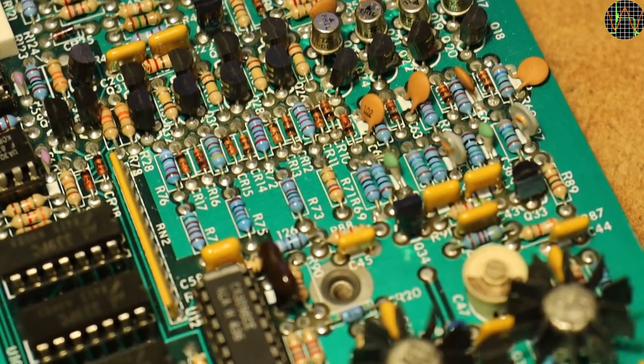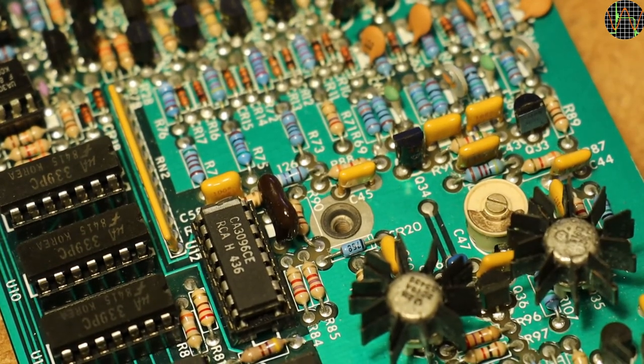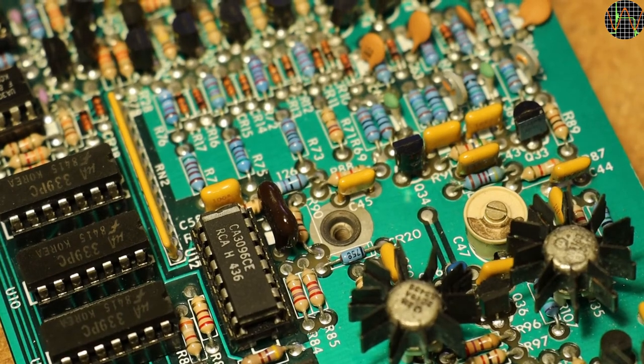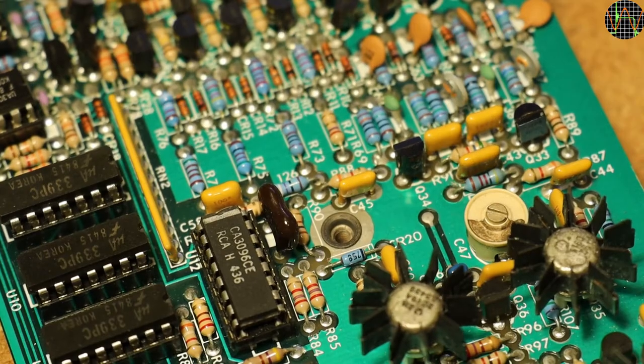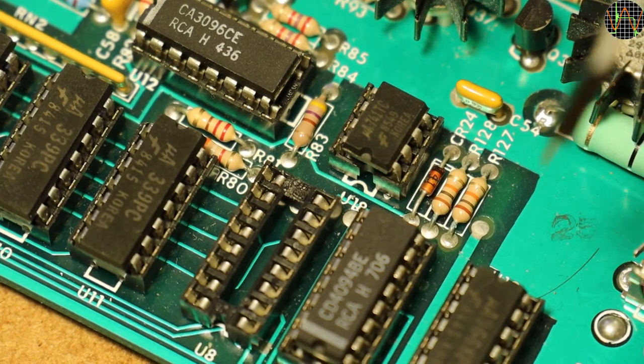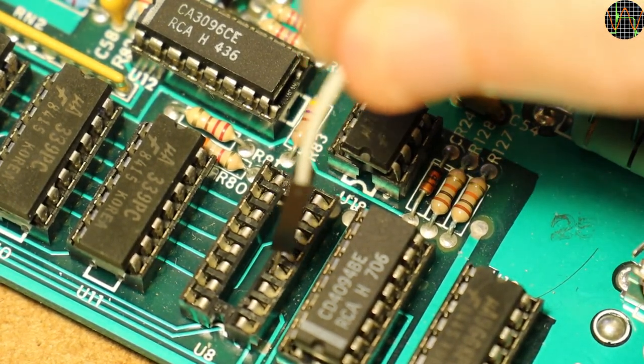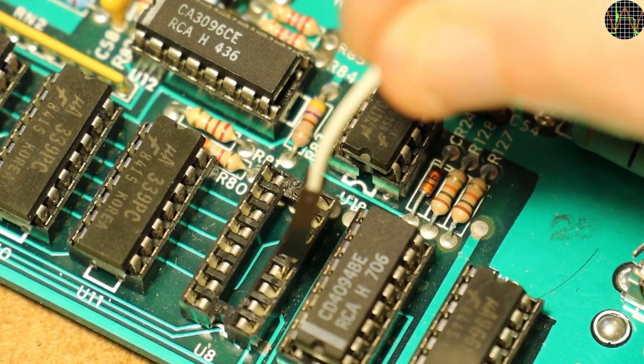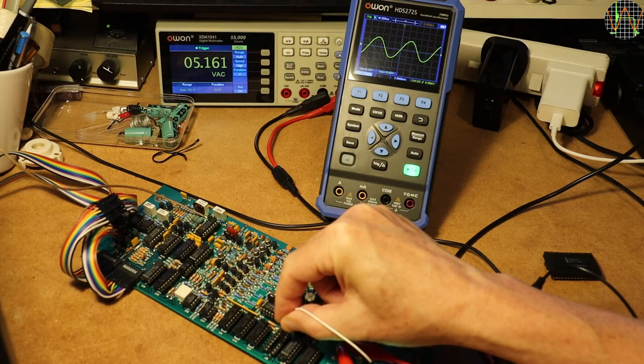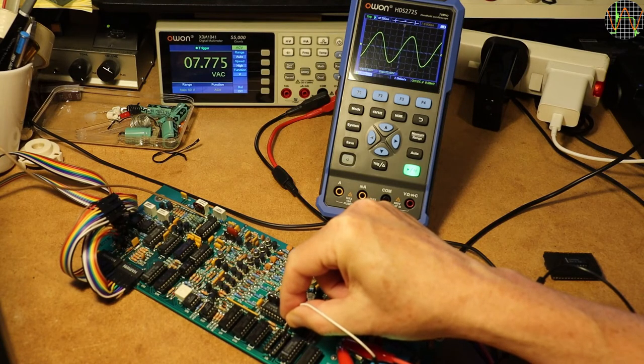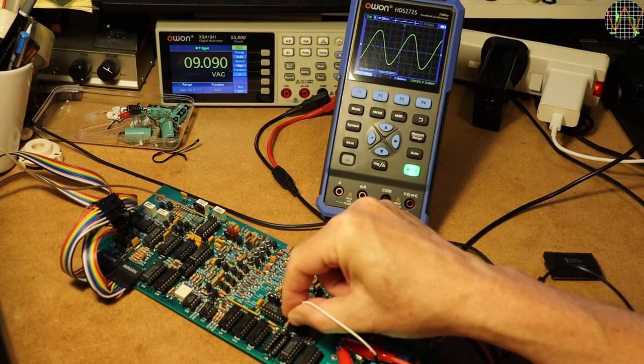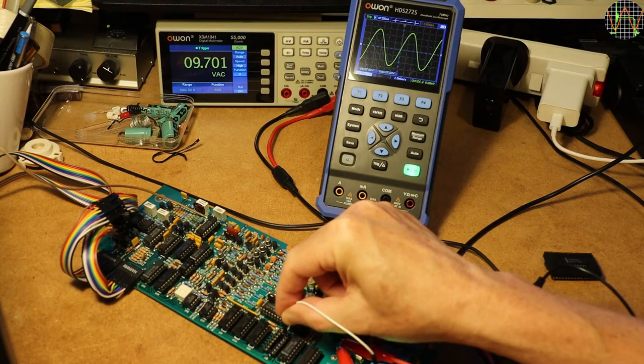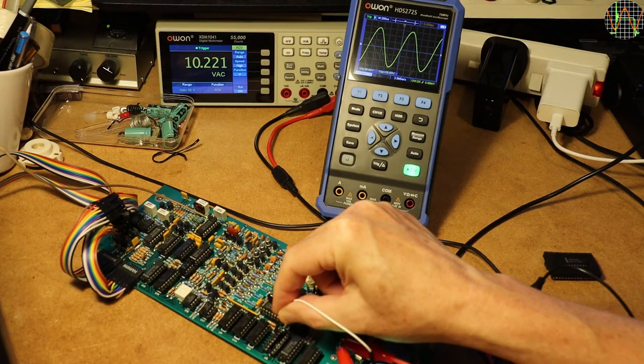The MOSFET switches connect either the signal or some resistance to the divider and they are switched in combinations which makes it very tricky to understand the effects. It is a rather dense part of the PCB with all the MOSFET switch pairs and the associated resistors, diodes and caps. The three LM339 comparators driving this set are on the bottom left. I spent many hours checking the circuit, solder joints, swapping LM339 and 4094 chips temporarily to see if the problem moves but it seems all in good order. My final test was to unplug the 4094 which is the equivalent of having all outputs high or selecting maximum output voltage and then pull each output of the 4094 to ground with a jumper wire. The full output of about 10.3V RMS is halved when Q1 is pulled down, reduced to 3 quarters for Q2, 7 eighths for Q3, 15 sixteenths for Q4 and so on in a nice binary fashion.